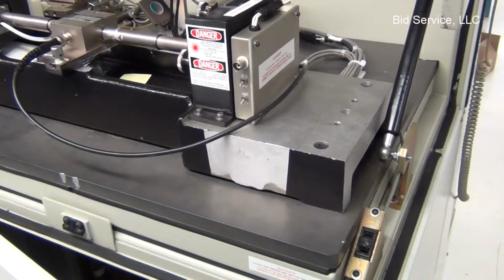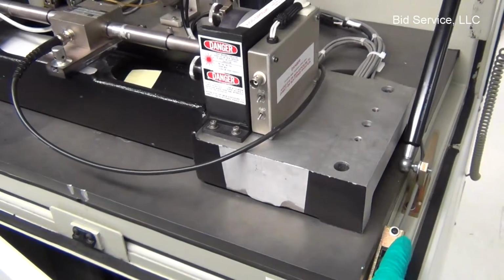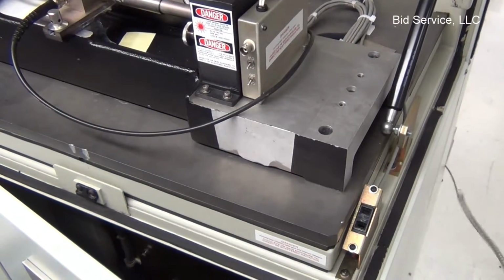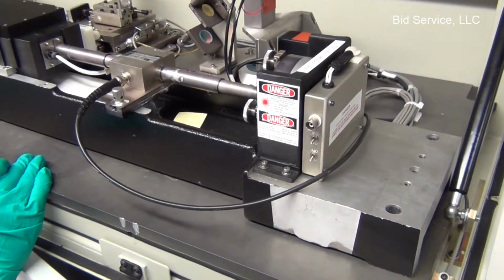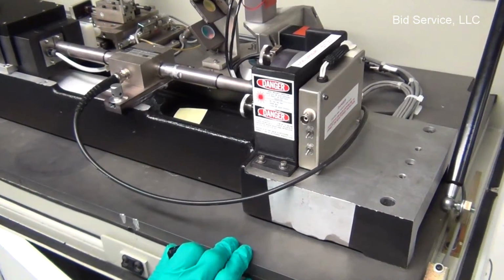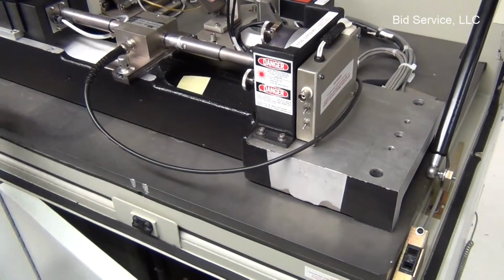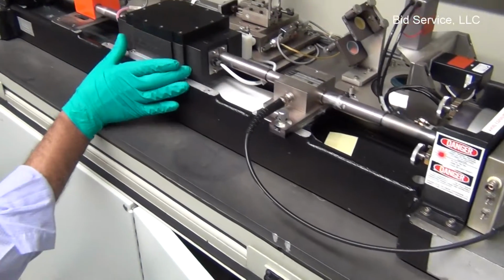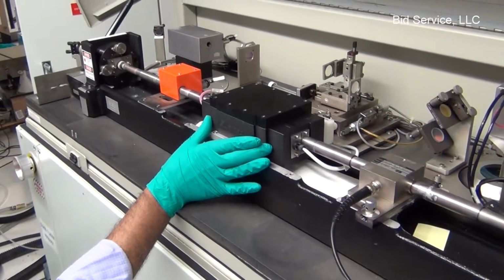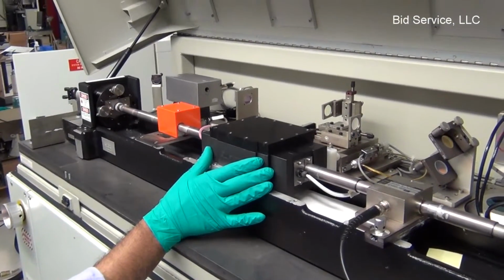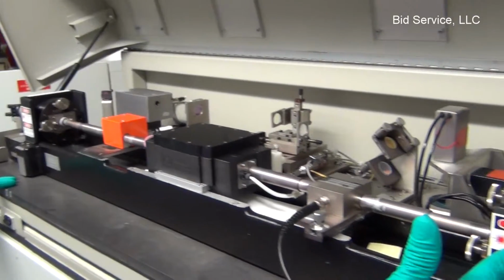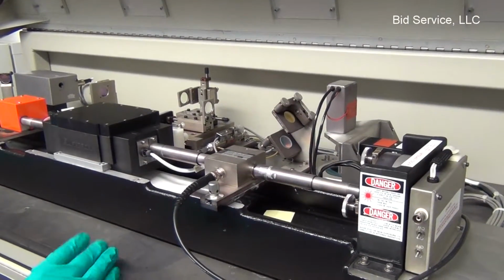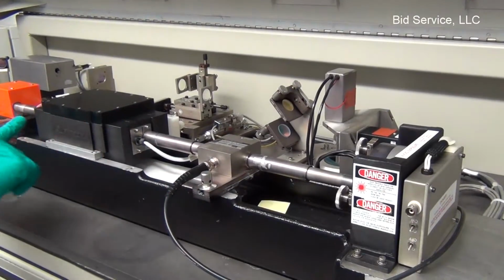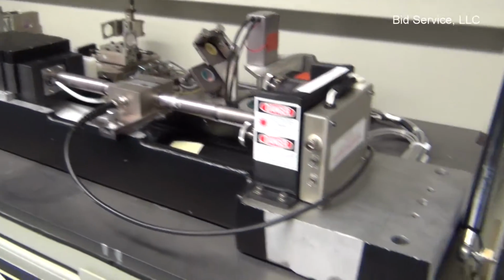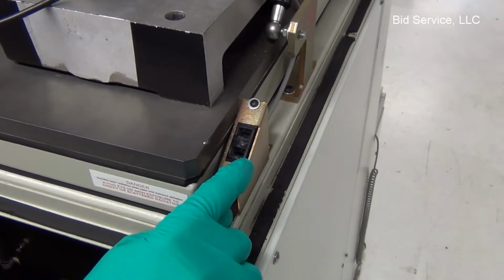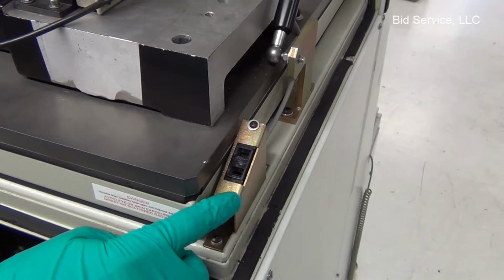Okay. This is the main laser optical bench here. The cover here has two interlock switches on either end. This is the main laser optical bench. With the YAG laser, this is the main lamp housing, and the rod is inside this, and this is the rear end mirror and the front end mirror, and there are tubes here which are shielding the actual light, and there are interlock switches at either end of this chamber.